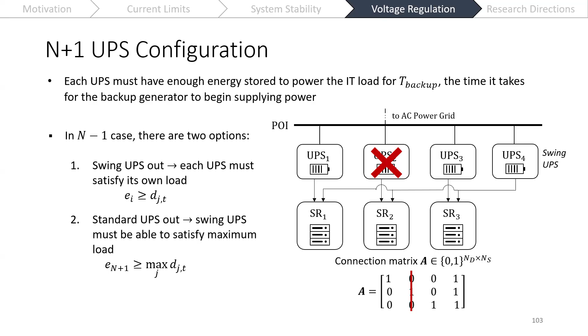In the case where one of the other UPSs, or the main standard UPSs, goes out, then the swing UPS has to be able to satisfy the maximum load that we have over those server racks, as it might need to satisfy whichever one its corresponding UPS goes out. So this simplifies the constraints that we have.